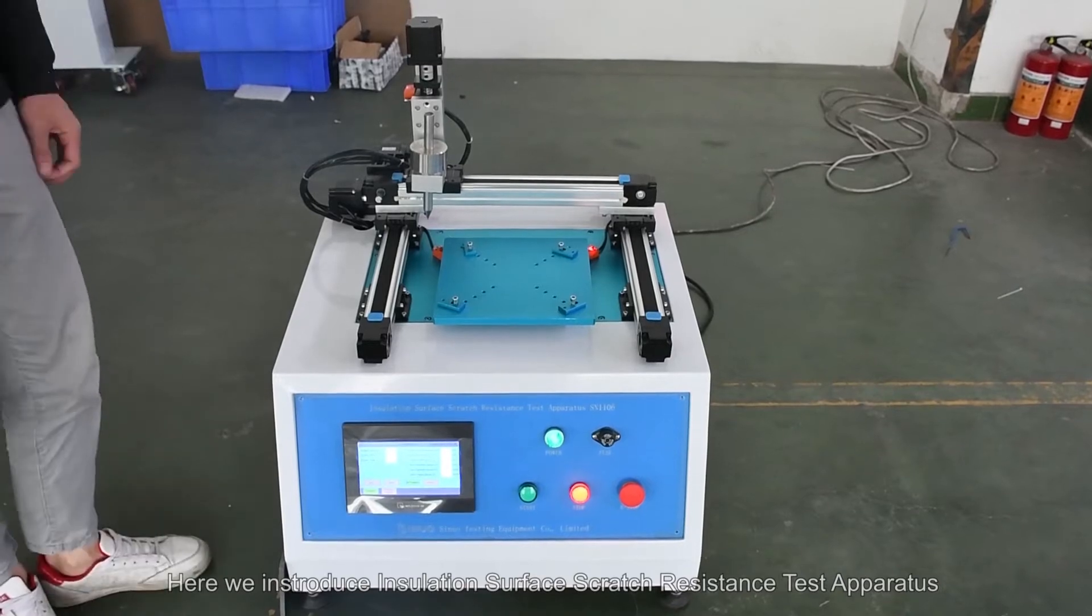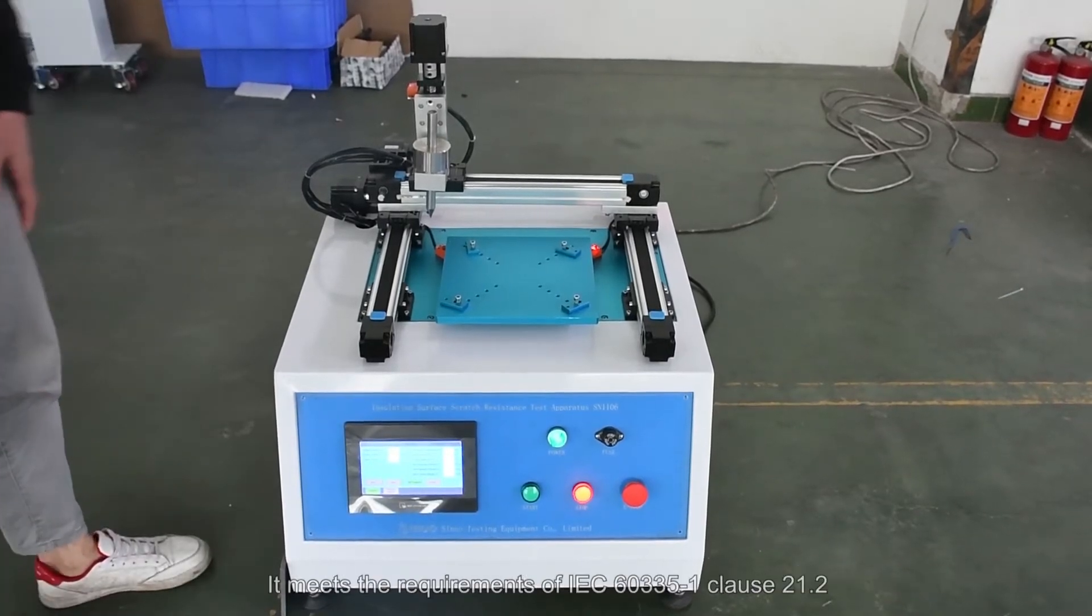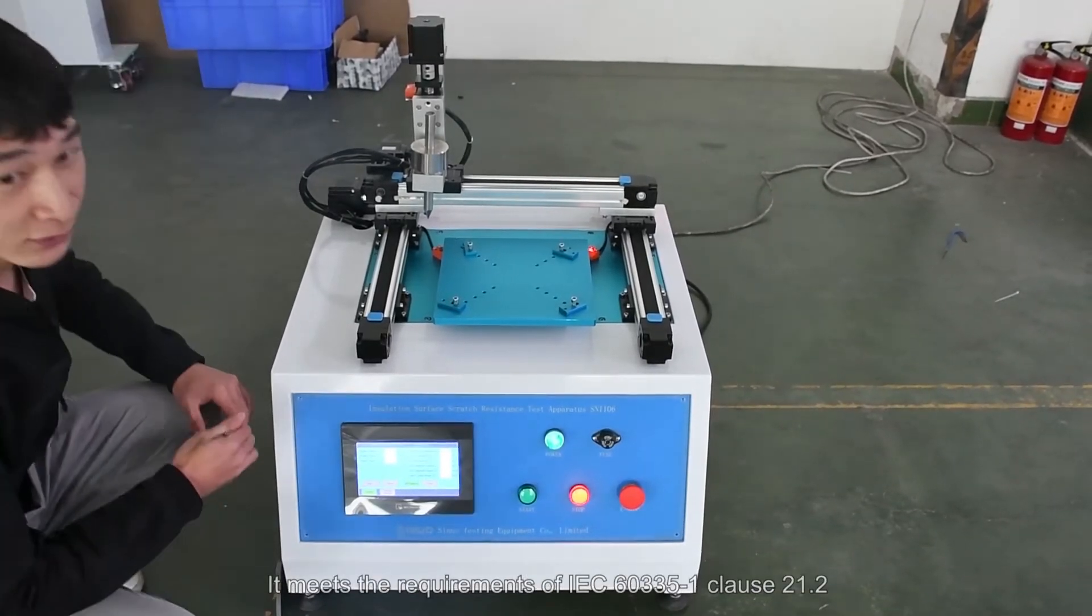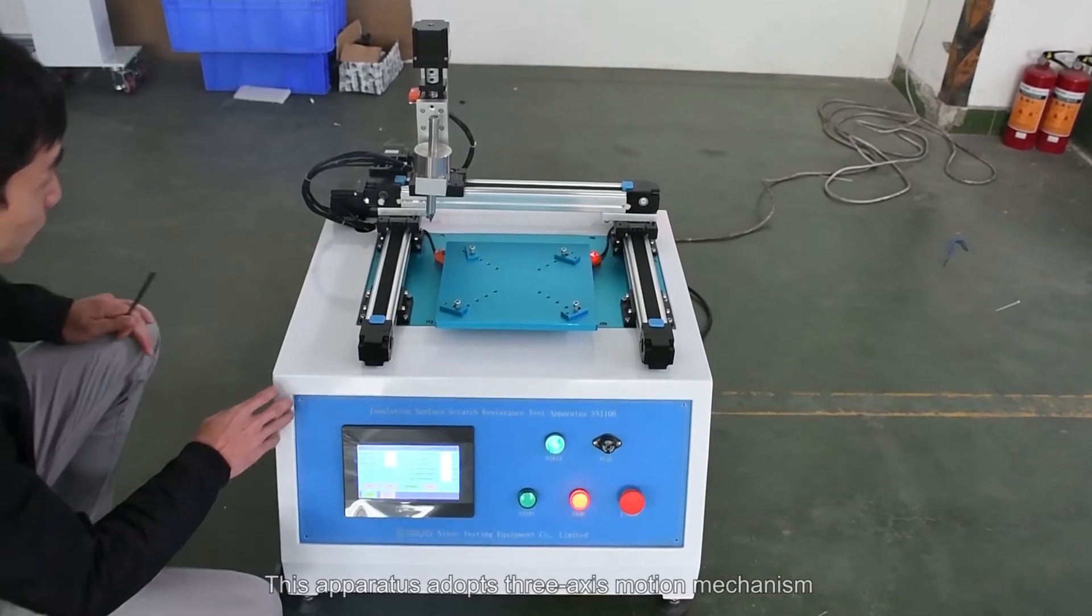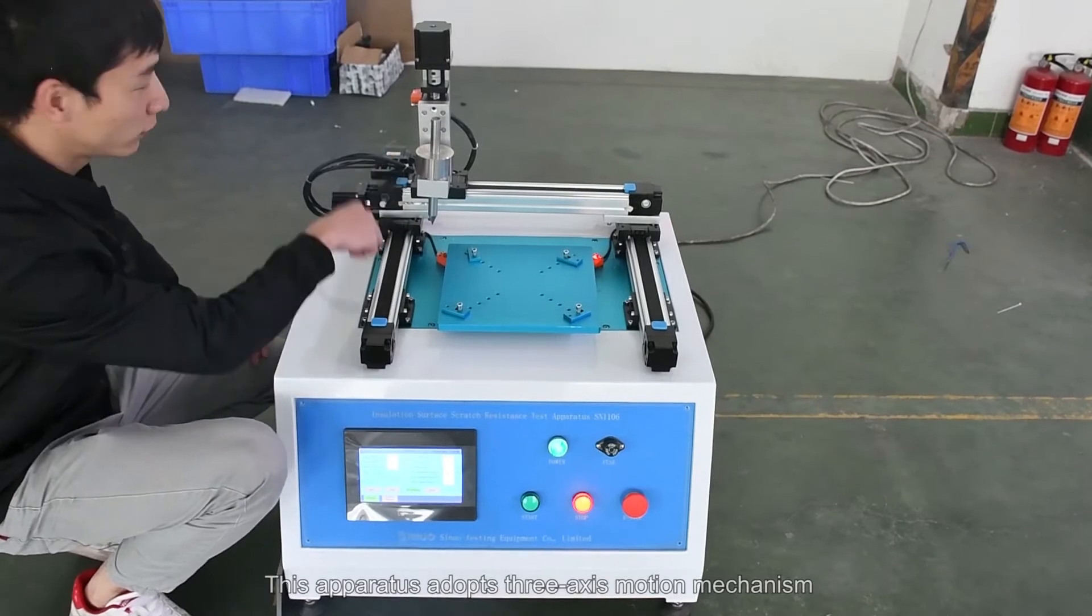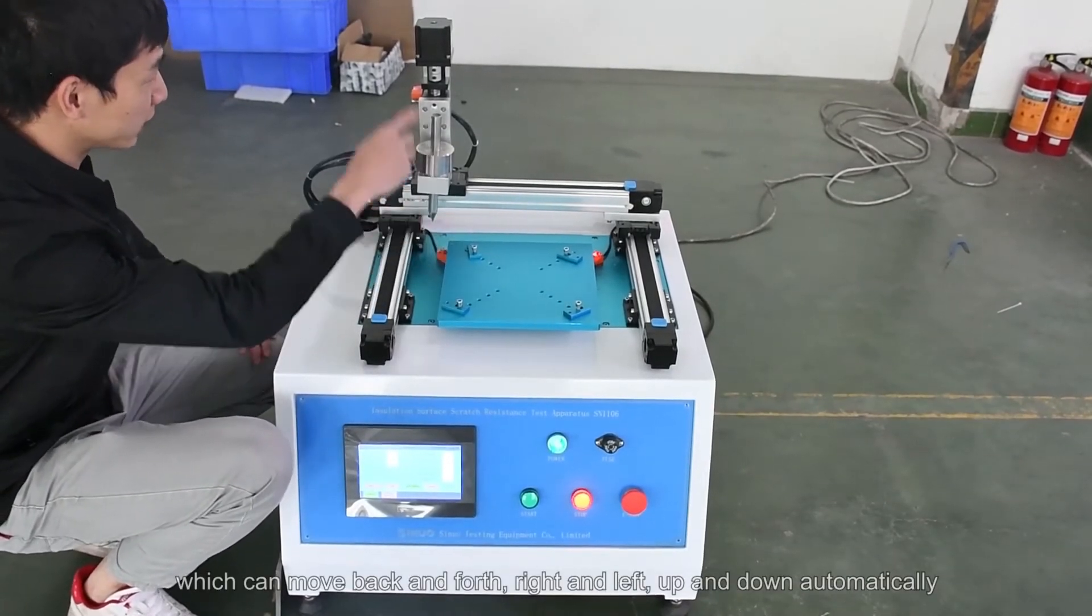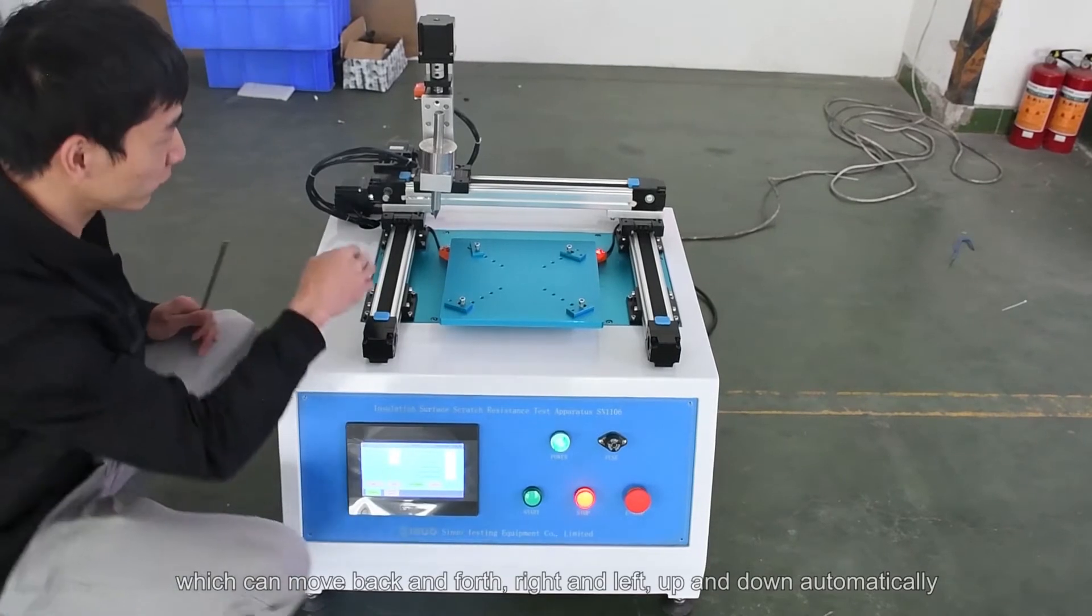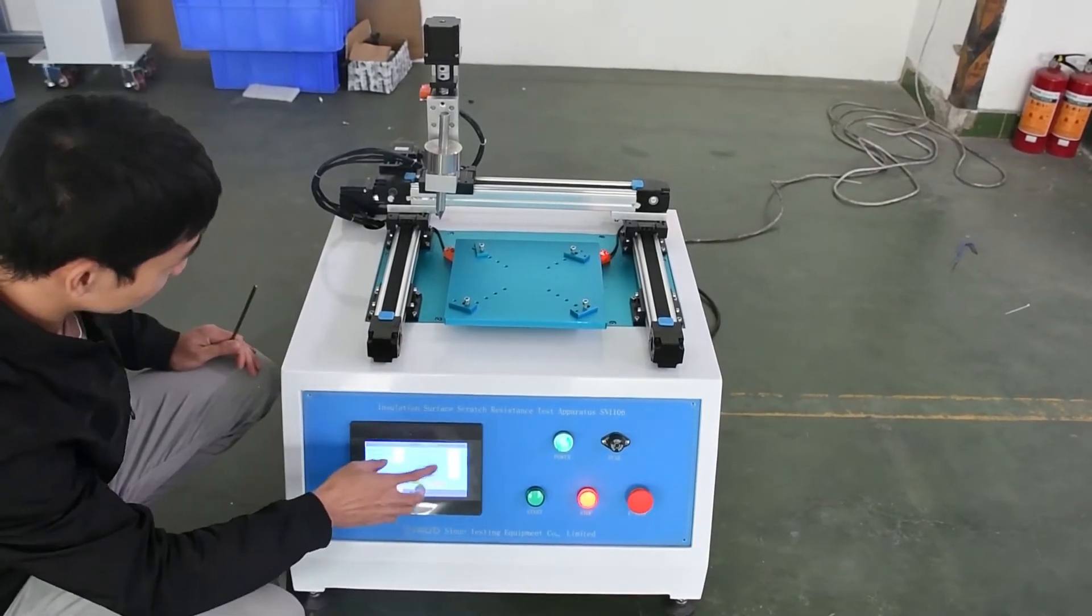Here we introduce insulation surface scratch resistance test apparatus. It meets the requirements of IEC 60335-1 clause 21.2. This apparatus adopts three axis motion mechanism which can move back and forth, right and left, up and down automatically.